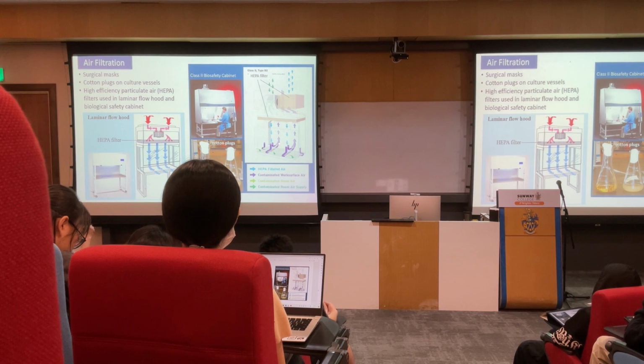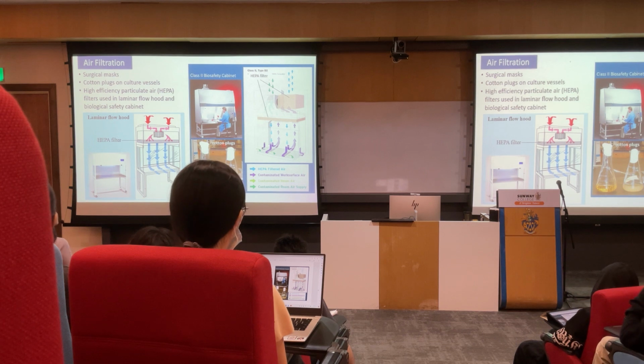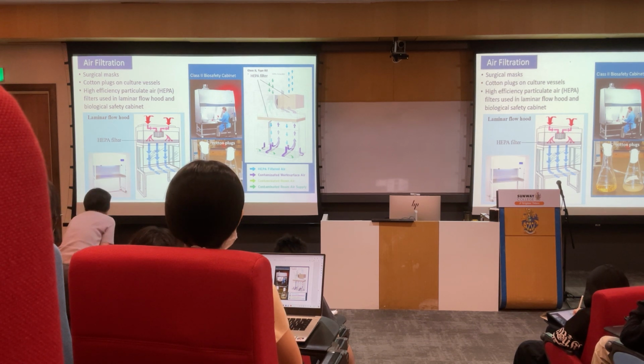It will actually recycle and be sucked up at the back. This purple arrow is sucking up the air, so the air will go to here. There is another HEPA filter, so it will trap anything, the microorganisms will be trapped by the HEPA filter. And then whatever comes out from the cabinet will be clean air. So the biosafety cabinet ensures that the air going in is clean and whatever comes out is clean. There is no contamination to the environment. So ideally, this is something that you can use to work with living tissue or living organisms. Okay, clear?